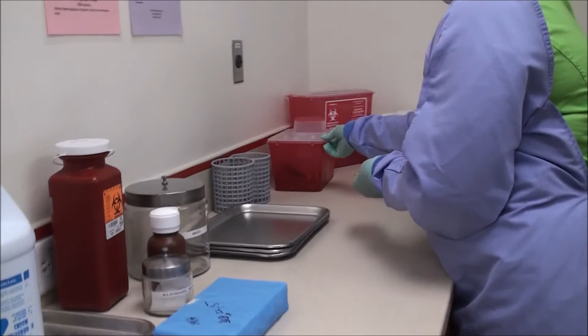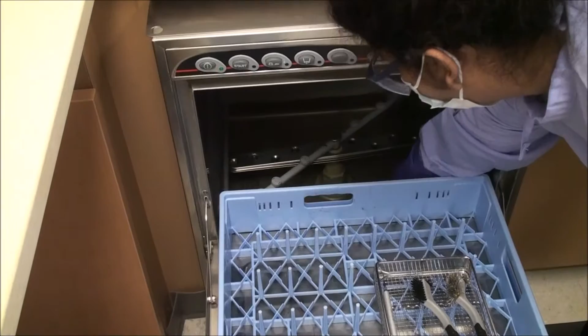At the end of the clinic session, turn the on-off push button. Remove the overflow plug. Push rack in and close the washer door. Press the drain pump push button until all the water has completely emptied from the wash tank.